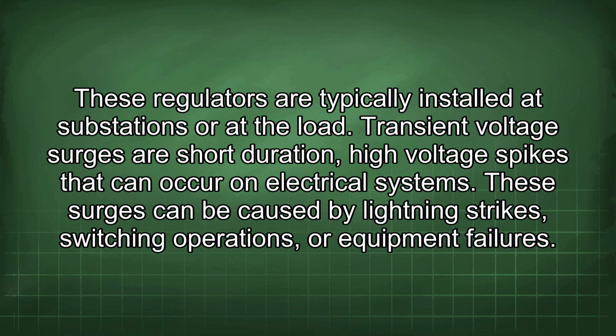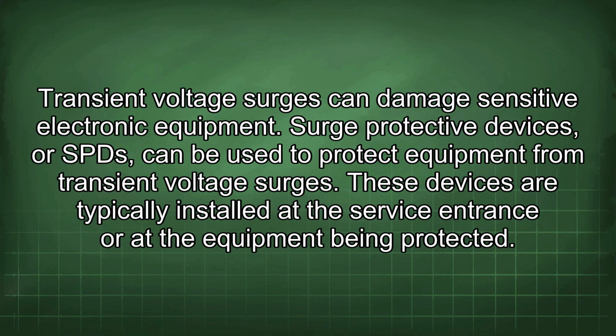Transient voltage surges are short-duration high-voltage spikes that can occur on electrical systems. These surges can be caused by lightning strikes, switching operations, or equipment failures. Transient voltage surges can damage sensitive electronic equipment. Surge protective devices, or SPDs, can be used to protect equipment from transient voltage surges. These devices are typically installed at the service entrance or at the equipment being protected.